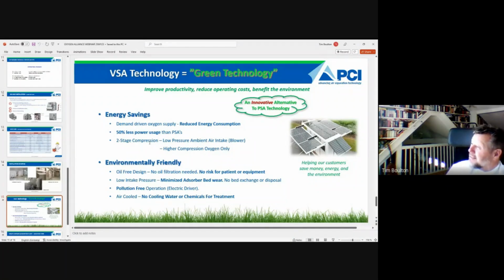VSAs are oil-free design. PSAs can be oil-free design, but that makes them, as we've heard before, a lot more expensive. Oil-free means that you need no filtration. There is no risk of oil contamination to either patients or equipment. You have a low pressure intake, which means you do not need to dry the air, and it minimizes the adsorbent bed wear. Because if you're going in with 7 bar, that also has a certain grinding effect on the zeolite, which means that after 5, maybe 7 years, if you're lucky, you'll probably need to exchange the zeolite in the PSA beds.